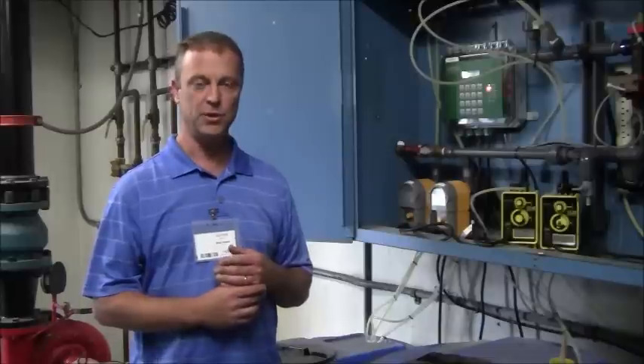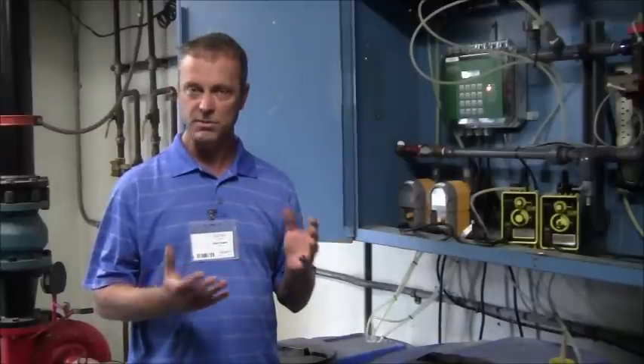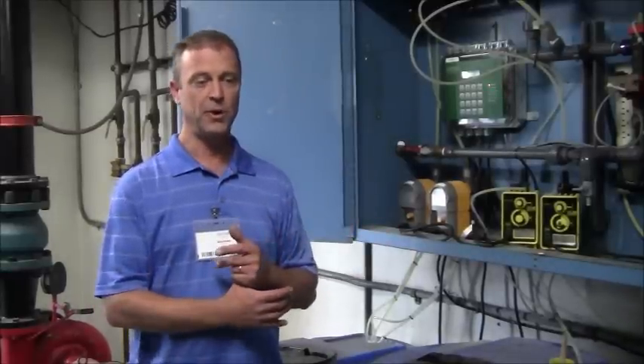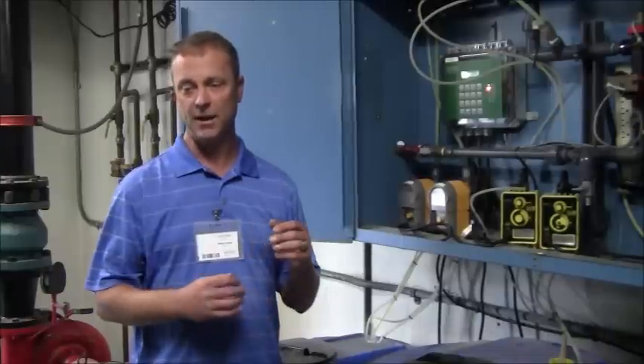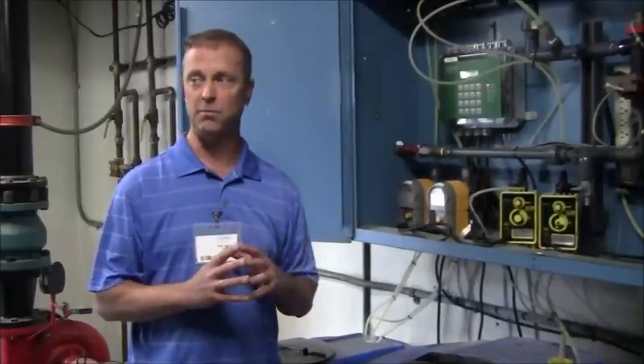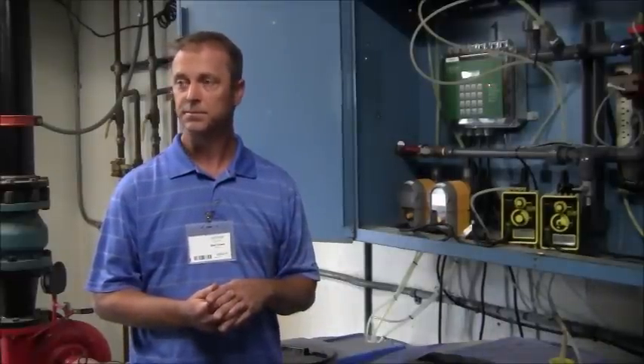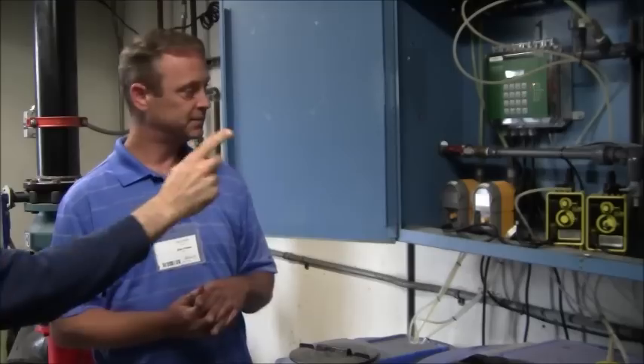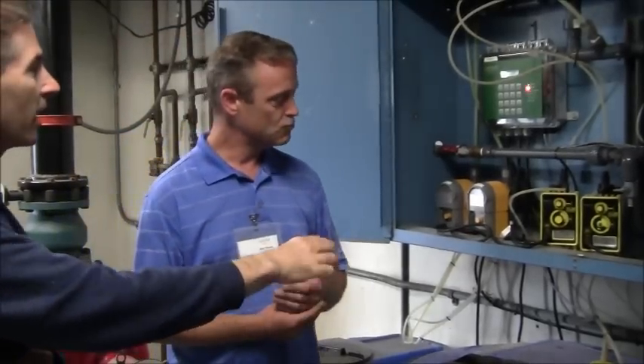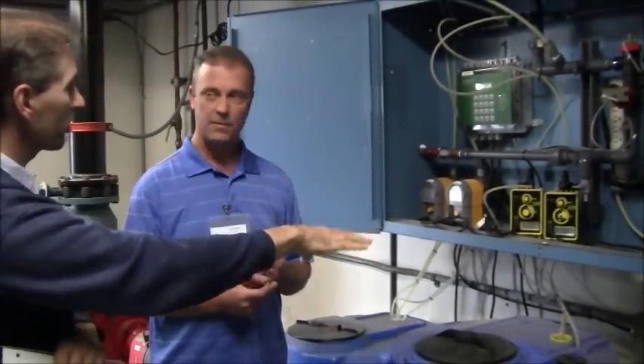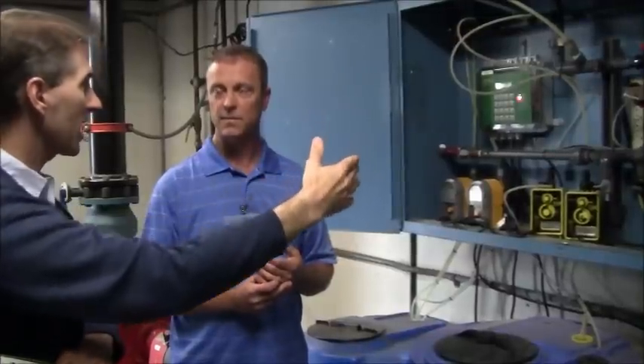You also have chiller barrels with yellow metal, typically copper tubes. So we have azole in the product, and that protects the yellow metals from corrosion and scale. Okay, great. And so that inhibitor product is going to get fed after every post-bleed that we do when the TDS gets up, when the tower is running.